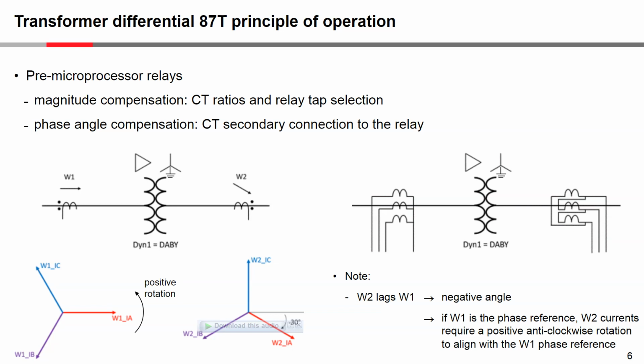Okay, and then if you look at the picture on the right, you'll see what was typically done for pre-microprocessor-based delta Y transformers. You can see from this that the delta side was the chosen phase reference, because with the Y connection of the CTs, there's no change or rotation of the phase angle from the primary current flowing into the transformer to the secondary current that would be connected to the protection relay.